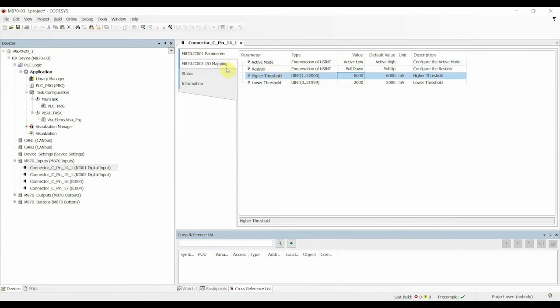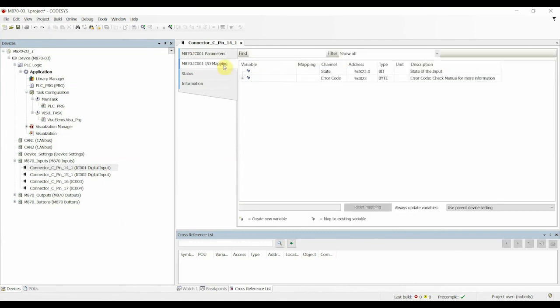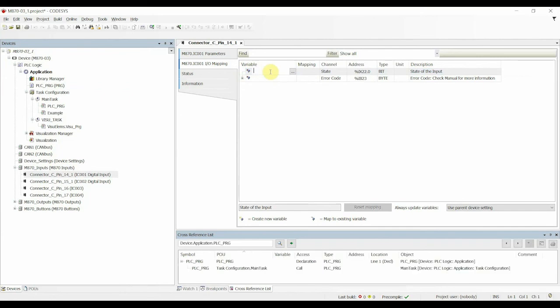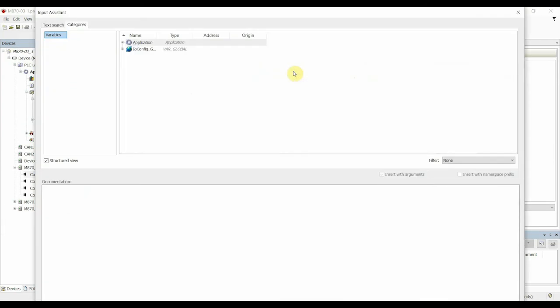To change the IO mapping, click here. And you can then map a variable within your application to the state of the digital input. To do this, simply click the three dots shown next to the variable. This will then bring up the POUs of the application. We can then select a boolean value associated with any POU in the application.